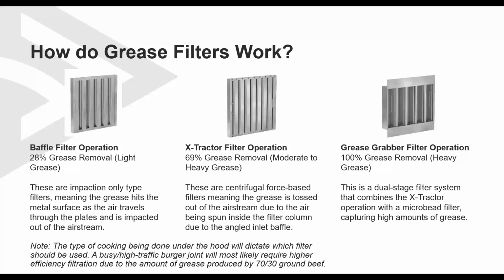So how do grease filters work? Here at Accurex, we have 3 different grease filtration options. Our standard baffle filter removes roughly 28% of grease. We consider this a light duty filter option. This filter works with impaction only, meaning the grease hits the metal surface as the air travels through the plates and is impacted out of the airstream.